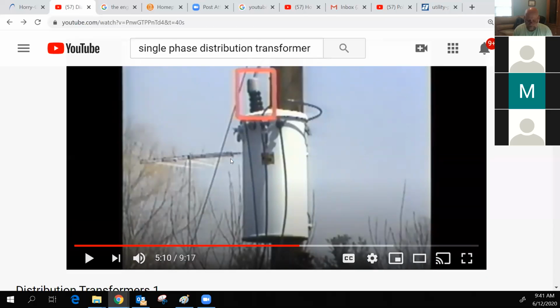open wire secondaries, they were still together. Of course, they would be slapping together down the line. You'd see a bunch of fire flying down the line. Or if it was a bigger internal fault, I have seen where when you close it back in, it would blow the top off of this transformer. You know, that had to be a really catastrophic fault inside for it to do that. But anyway, I have seen it done like that.